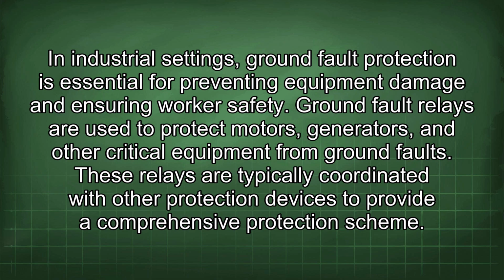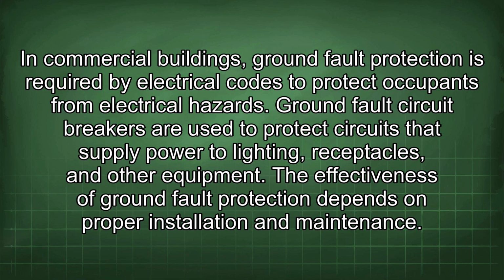In industrial settings, ground fault protection is essential for preventing equipment damage and ensuring worker safety. Ground fault relays are used to protect motors, generators, and other critical equipment from ground faults. These relays are typically coordinated with other protection devices to provide a comprehensive protection scheme. In commercial buildings, ground fault protection is required by electrical codes to protect occupants from electrical hazards. Ground fault circuit breakers are used to protect circuits that supply power to lighting, receptacles, and other equipment.